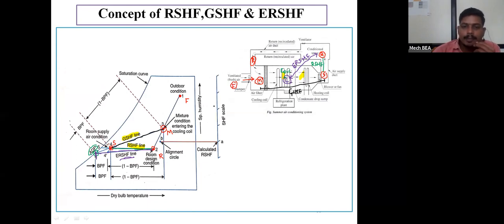So by considering the bypass factor, the coil condition here will be point C, which is called the apparatus dew point temperature. If I connect the apparatus dew point temperature, or coil condition, with the required room condition, then that line will be called the ERSHF line. Have you understood this concept? Yes or no? Write in the chat box.